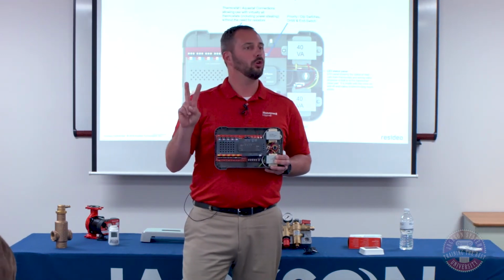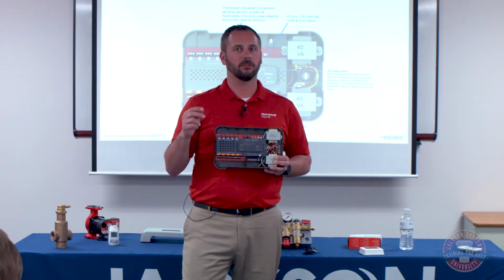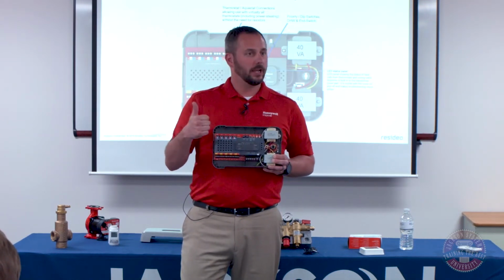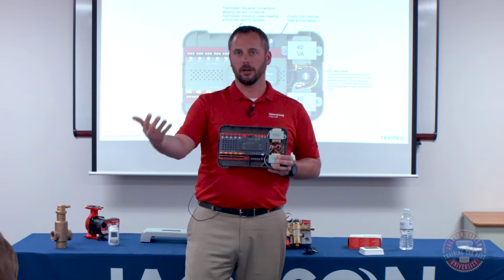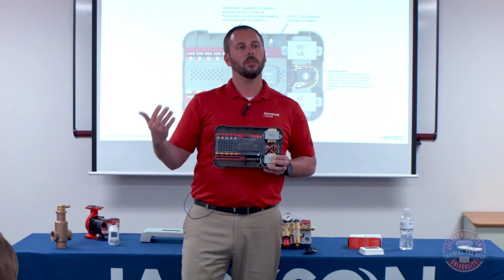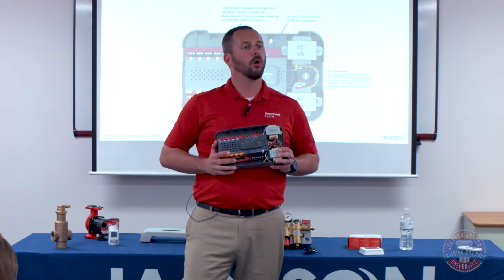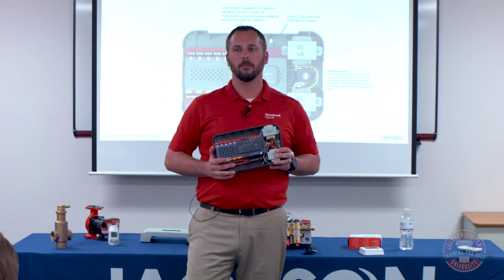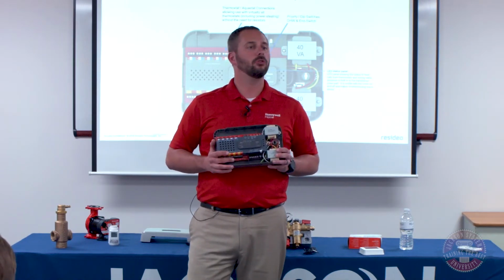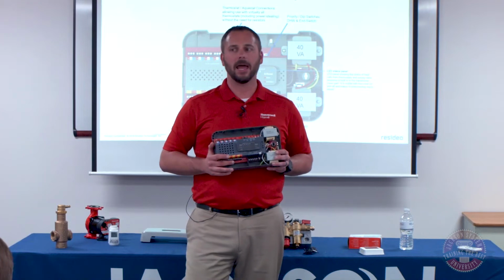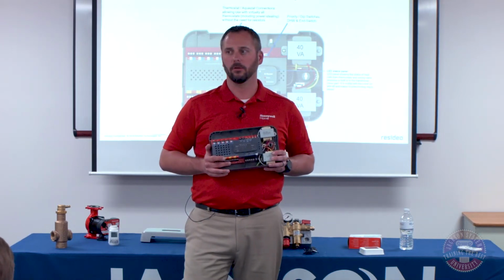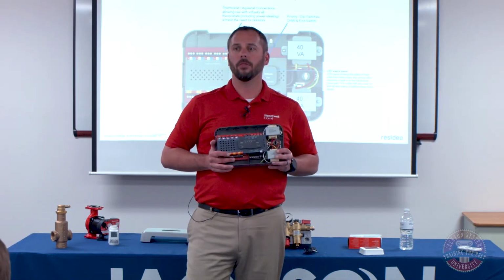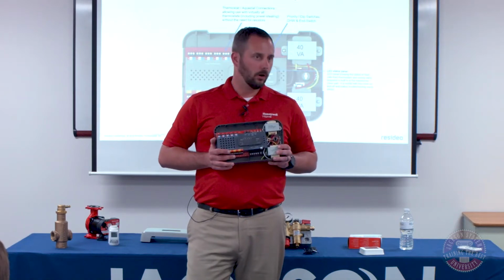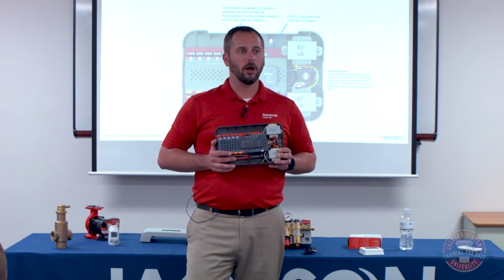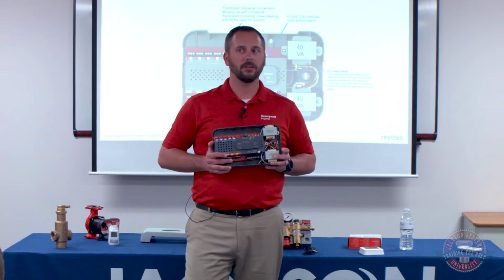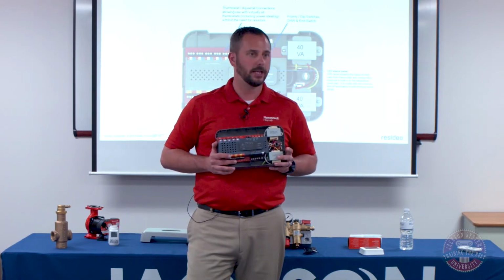You only need 2 if it's a simplistic hydronic system, R and W. I always recommend hooking up the C, which is going to be your constant power to the thermostat. The other reason I suggest that is there's more and more people migrating to smart home products. If you've only run 2-strand wire in the wall, it dramatically limits your thermostat availability and offering. If you run 3, all of our Wi-Fi thermostats work perfectly well off of 3 wires. So that C basically just powers the Wi-Fi radio inside of it.